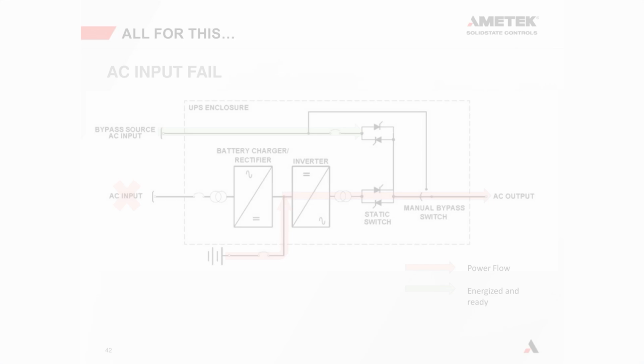Power will flow from the battery through the inverter, through the static switch, out to our AC outputs, and your load circuits will not see even a minute blip. You could analyze it down to the smallest portion of time and you won't see anything, because the battery just continues supplying power to the inverter. Our output is uninterrupted.